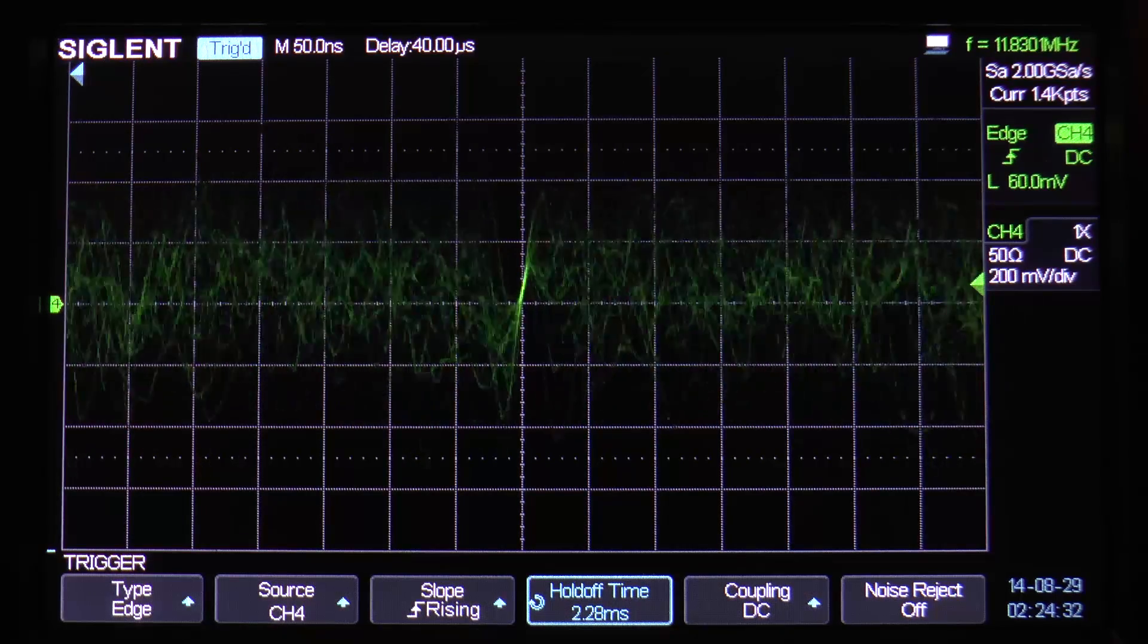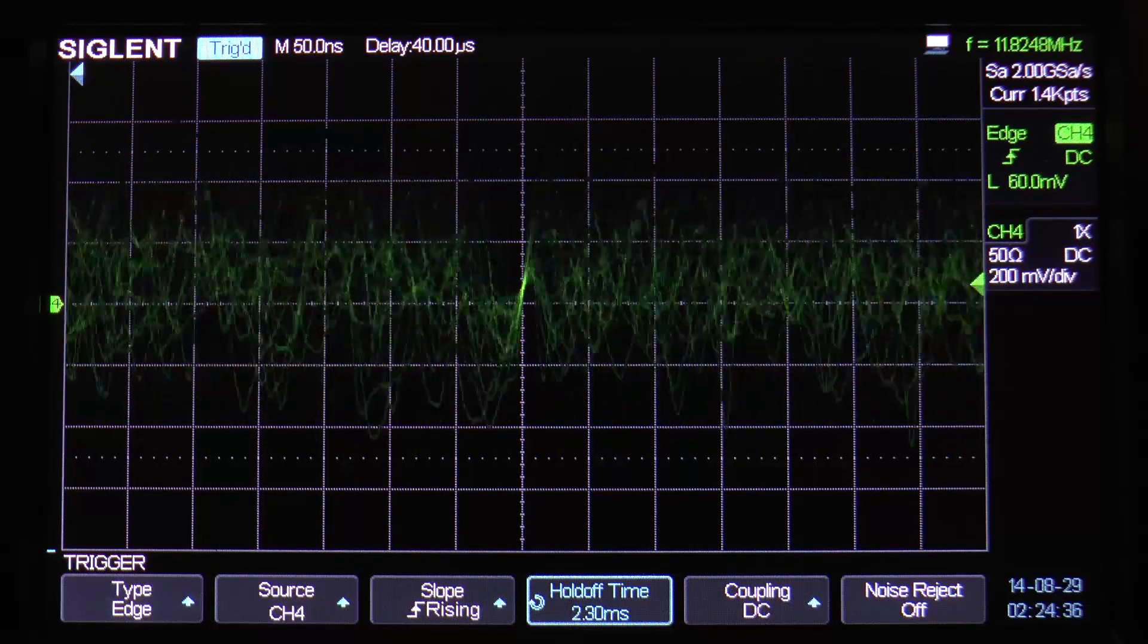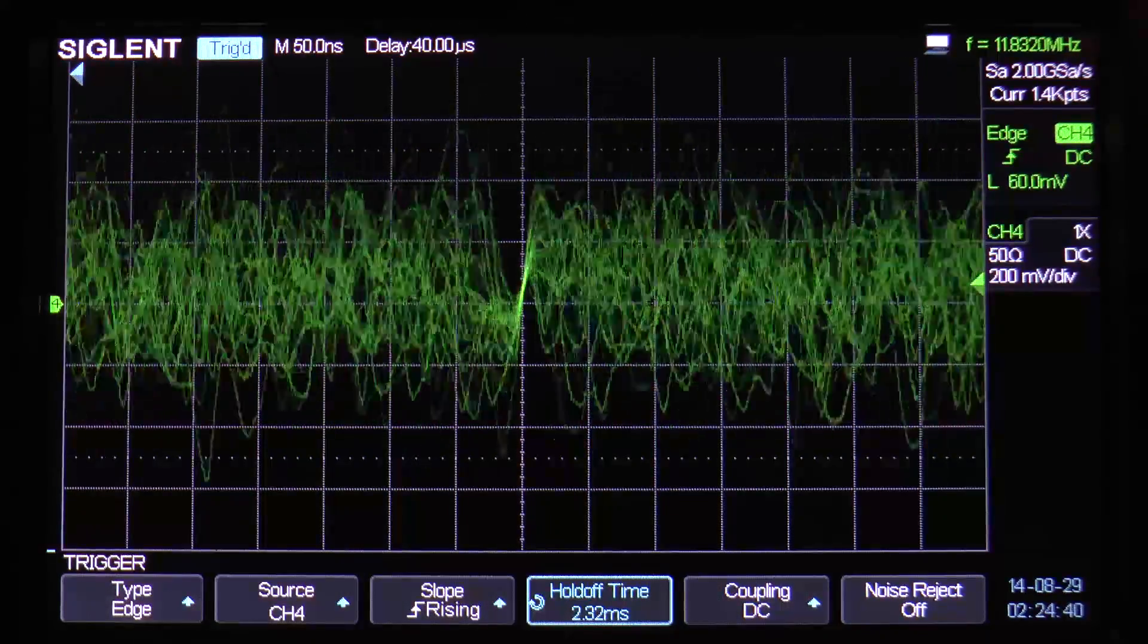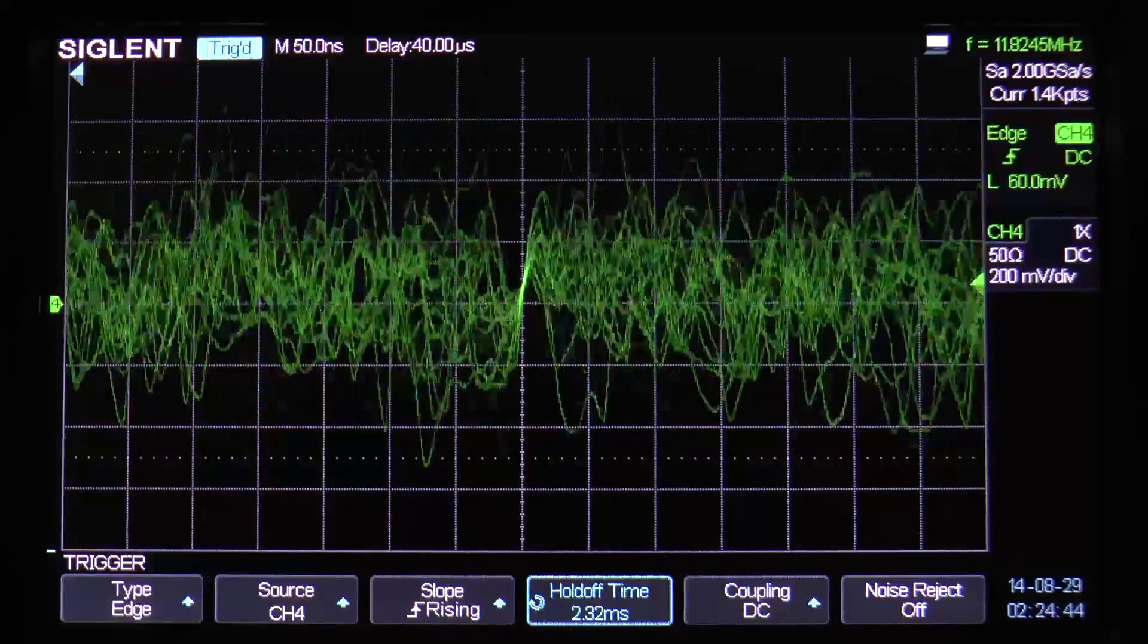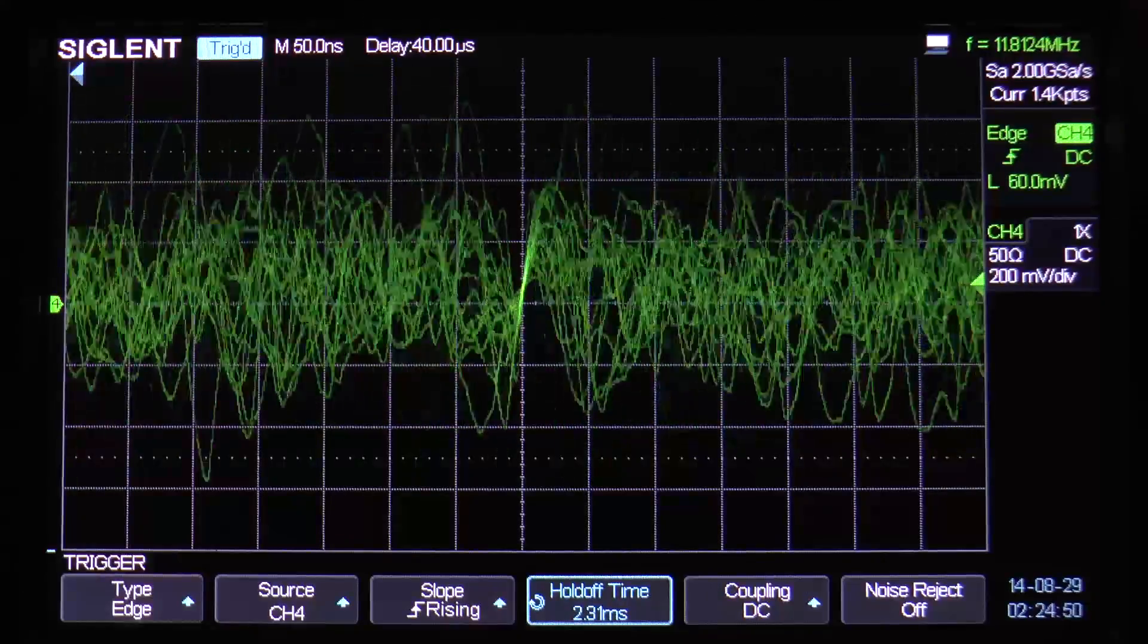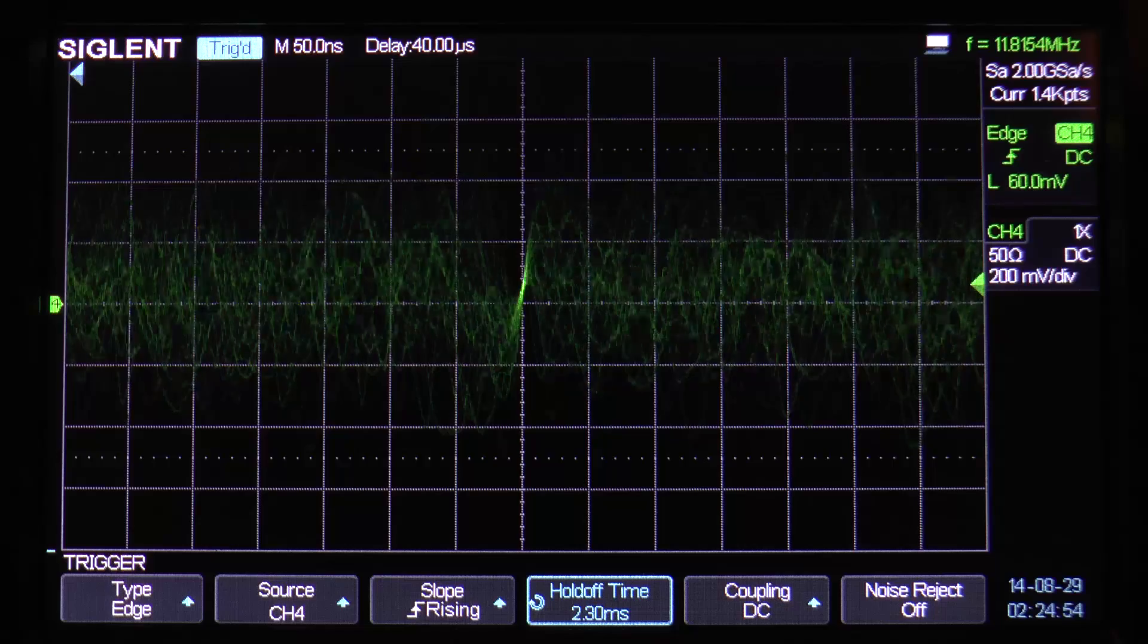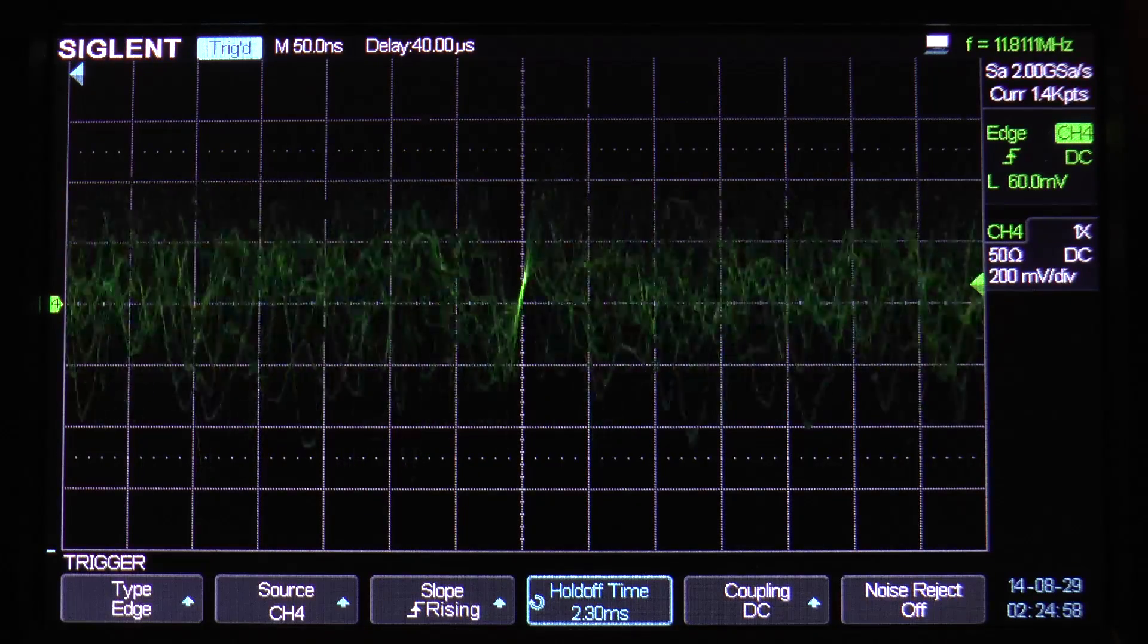When I change the holdoff time here, I can force the update rate slightly higher or lower, and you'll see we're right near the boundary where the intensity grading changes dramatically. We're at 430 waveforms per second. You see how drastically all of a sudden the grading changed because it dropped the number of levels dramatically. If I flip it right back up, there I'm at 432, 434, and all of a sudden the grading is much broader again.